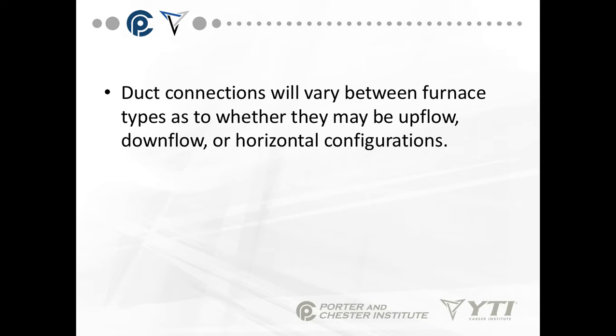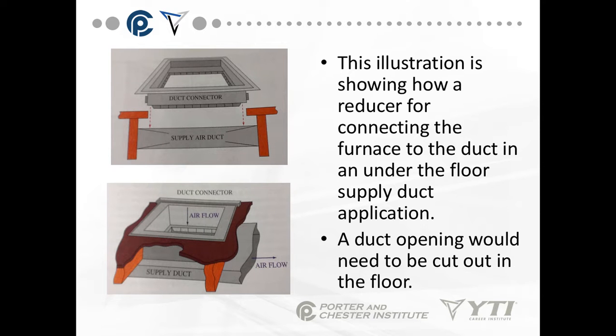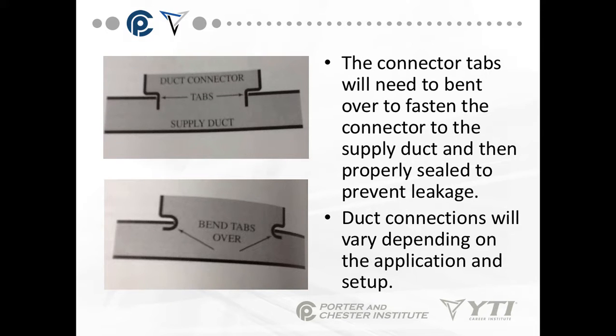Duct connections may vary between furnace types as to whether they're upflow, downflow, or horizontal configuration. This is an illustration showing how to use a reducer for connecting the furnace to the duct in an under the floor supply duct application. A duct opening would need to be cut out in the floor. The connector tabs would need to be bent over in order to fasten the connector to the supply duct and then properly sealed to prevent leakage. Duct connections will vary depending on the application and the setup.